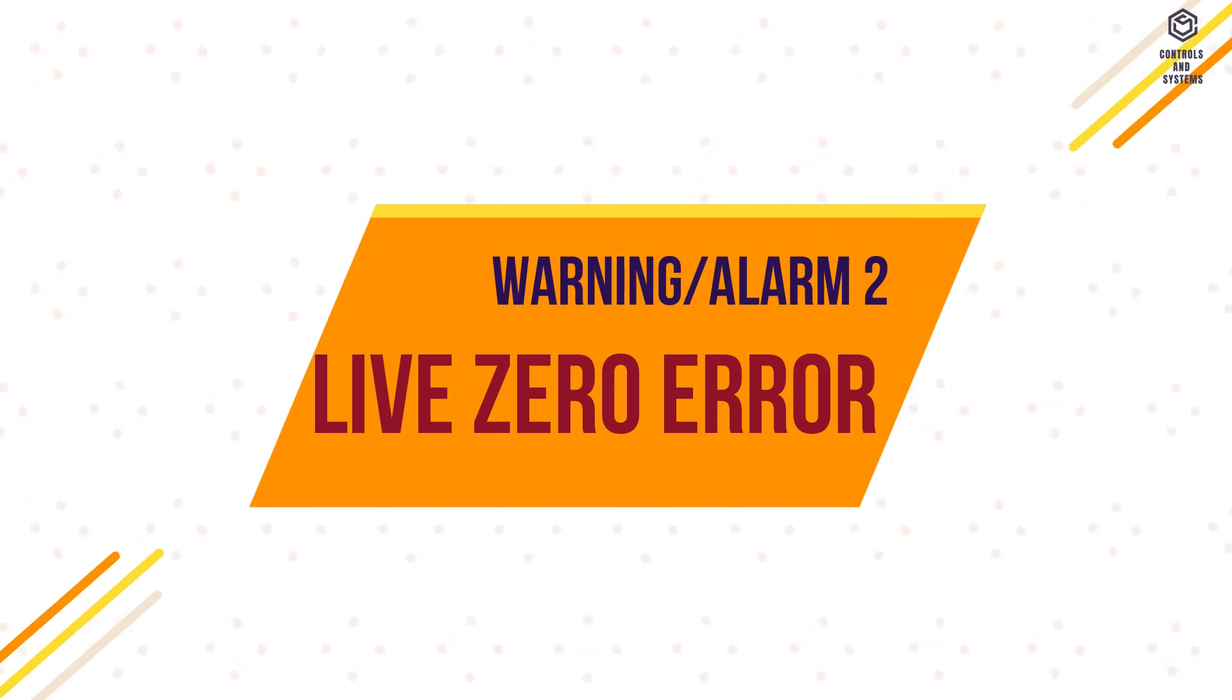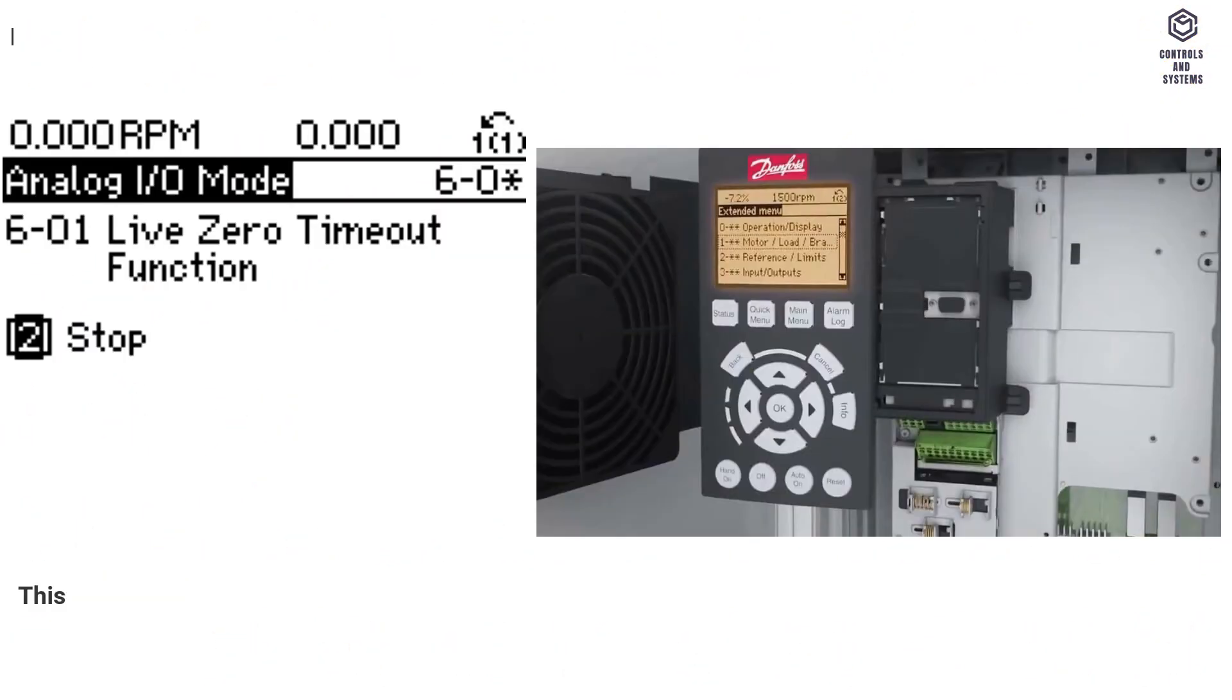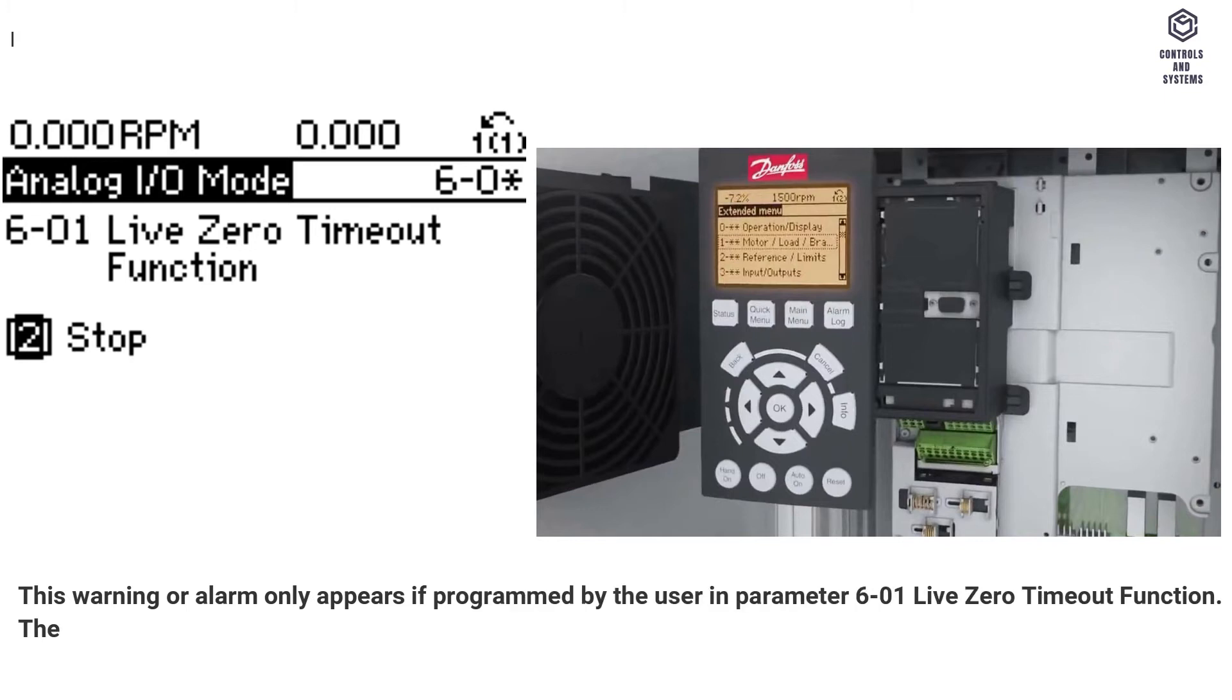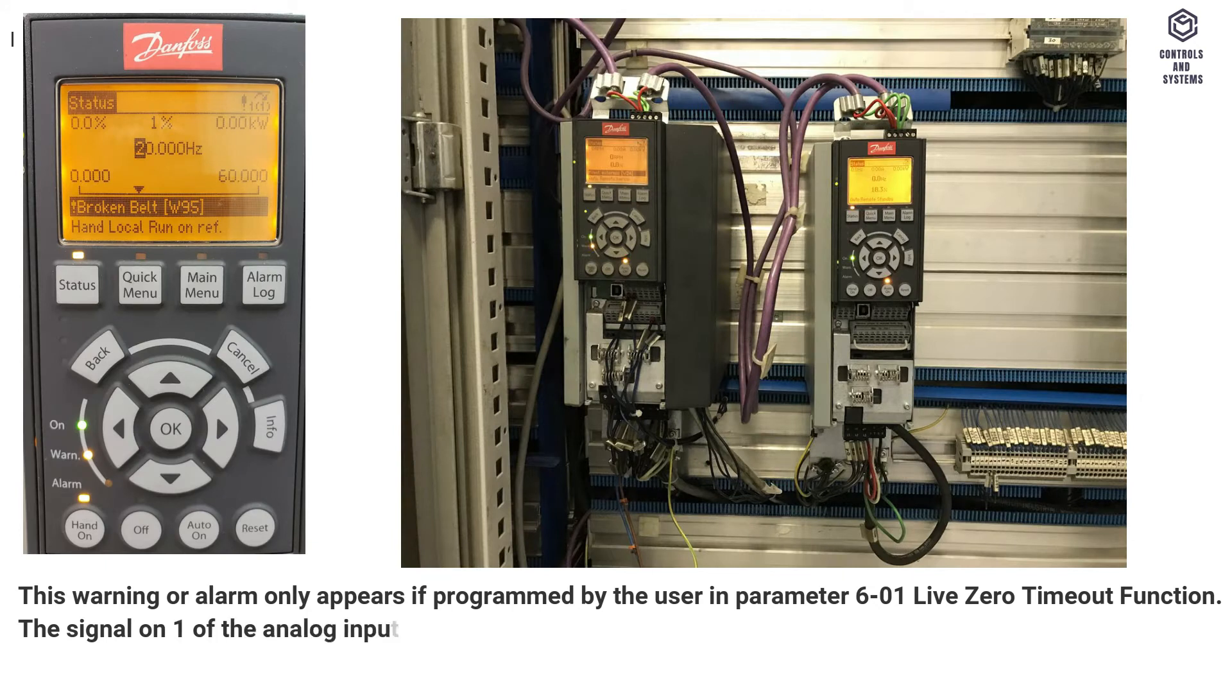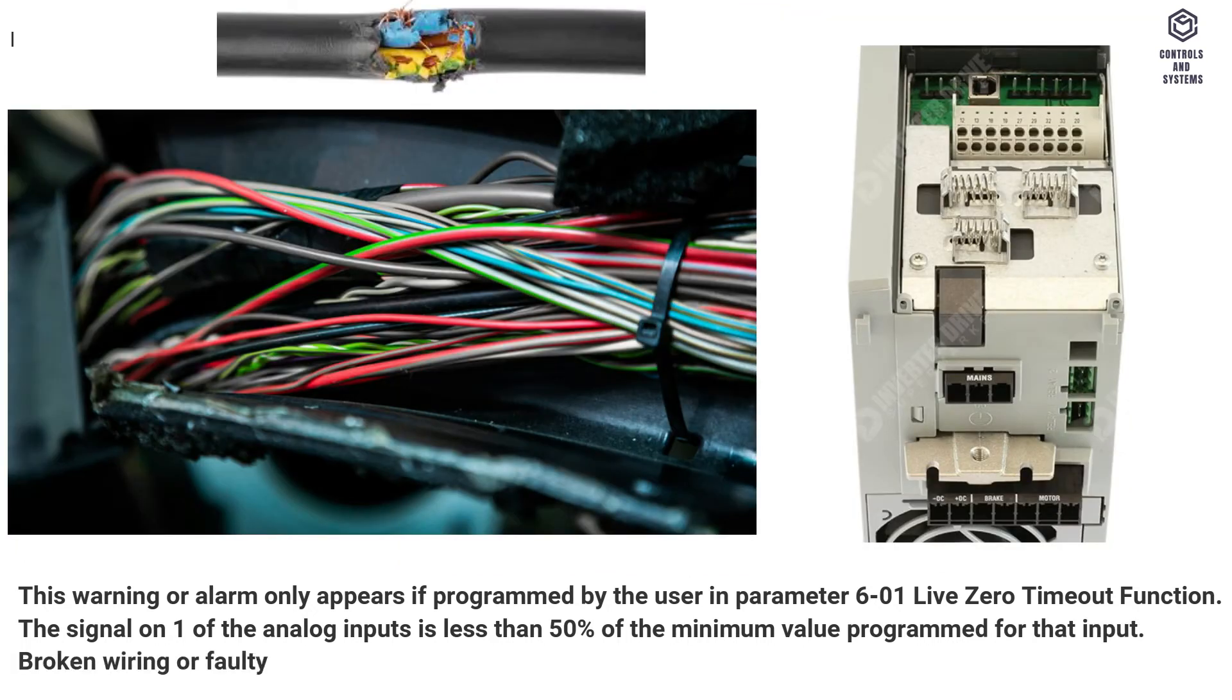Warning, Alarm 2, Live Zero Error. This warning or alarm only appears if programmed by the user in parameter 601 Live Zero Timeout Function. The signal on one of the analog inputs is less than 50% of the minimum value programmed for that input. Broken wiring or faulty device sending the signal can cause this condition.